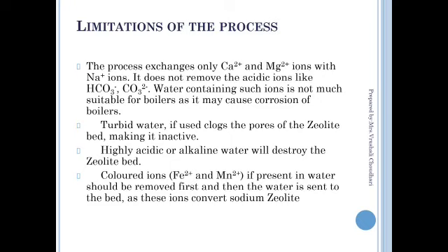The process exchanges only calcium and magnesium ions with sodium, but it does not remove the acidic ions like CO3 2-, HCO3-, that is the carbonate and bicarbonate ions. So water containing such ions is not suitable for boilers as it causes corrosion to the boilers. If turbidity particles are present in hard water, they are going to block the pores of zeolite and make it inactive.